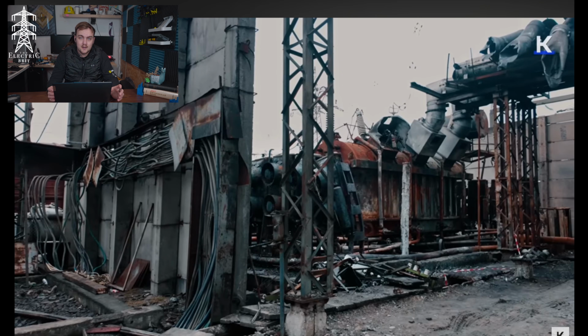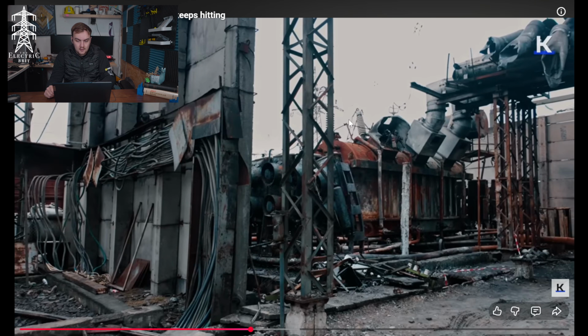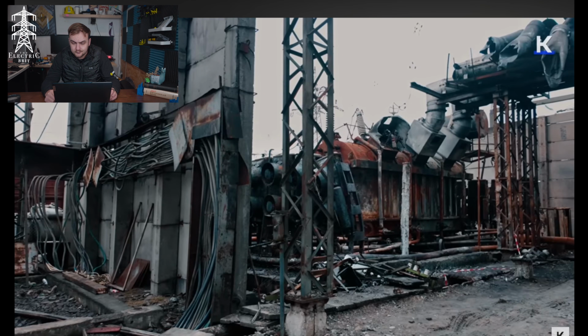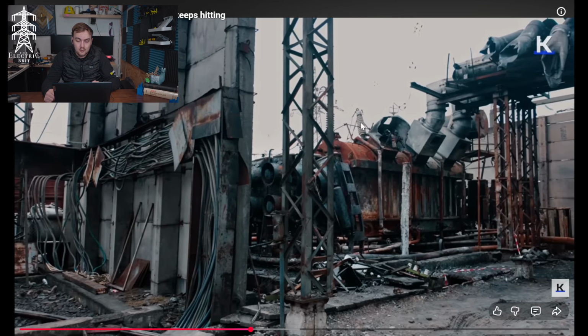Talking about North Hyde again, you had two transformers right next to each other with nothing separating them. When one failed and caught fire, the shrapnel damaged the other transformer right beside it, because the bushings on top - you can just see one on the far side of this transformer here - are typically made of porcelain or glass. In the UK usually porcelain, and it's quite fragile. So if one of these blows up, or debris comes flying across and hits it, it's going to smash it, causing a short circuit, and it could flash over and quite destructively blow up.